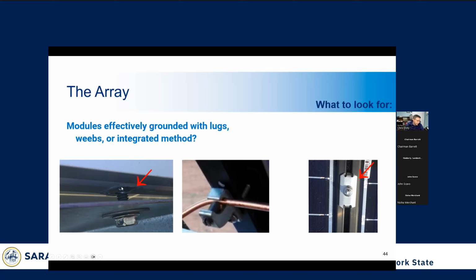And on the left, you can see this is just a kind of a poor installation. You can see the screws coming out. It wasn't tightened very well. That can eventually come disconnected, and it could potentially change the ground path throughout the system. And so it's critical that the equipment that's used to bond and ground the system is suitable for the environment and the application.